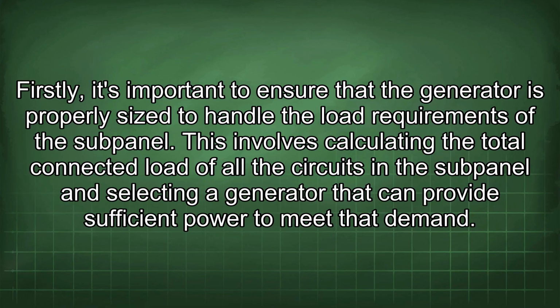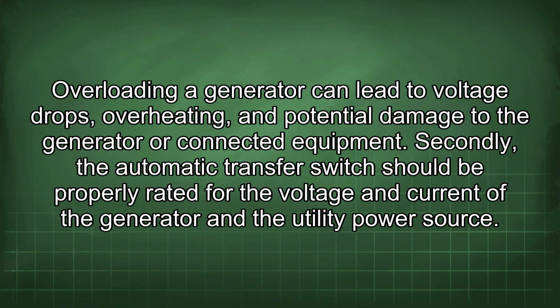This involves calculating the total connected load of all the circuits in the subpanel and selecting a generator that can provide sufficient power to meet that demand. Overloading a generator can lead to voltage drops, overheating, and potential damage to the generator or connected equipment.